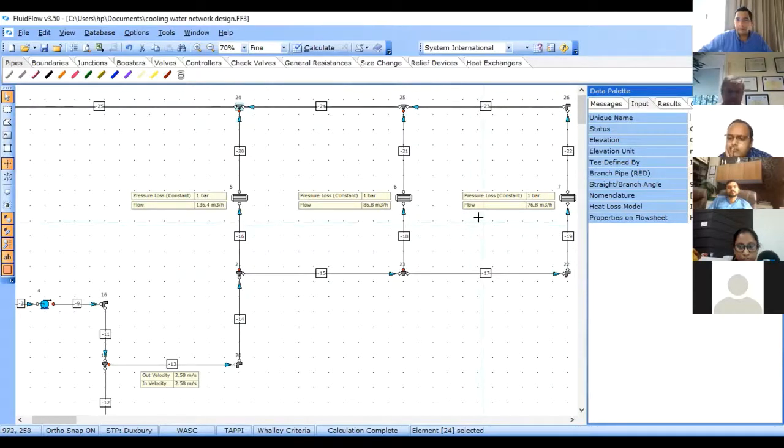This is a very important step because this water imbalance problem is extremely common in the cooling water system of any operating company. We recently completed one project for Bharat Oman Refineries Limited in Madhya Pradesh in India. They had 170 heat exchangers. We modeled the entire cooling water system for their refinery. The first step was to establish the existing system, right? Then, what is the problem that they have got?